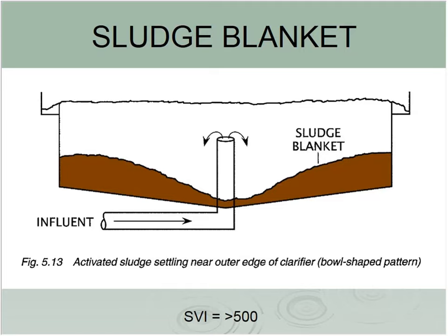It's what happened to me. And typically, as your sludge blanket rises, one of your controls is you increase your return sludge flow, pull it out of the tank, so you find out what's really going on. It's one of the first moves you make. Well, as I did that, I increased the flow, but again, the flow is going to be right here by this incoming pipe, pulling material away. Apparently, the increase in flow just exacerbated the problem, and it prevented stuff from coming down. I was just rat-holing through here. Material just kept staying on the outer periphery of the rakes. And I just get these big blobs of stuff come floating to the surface and drive us crazy. Finally kind of figured out what might be going on, and got way back on my return sludge flow. And within 12 hours, all the material moved back down where it should be. I was able to pull it out of there.